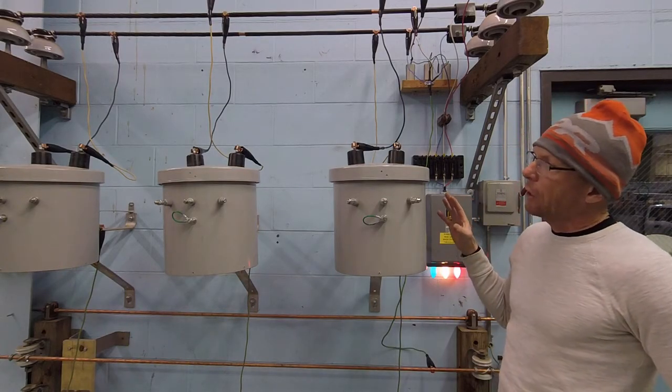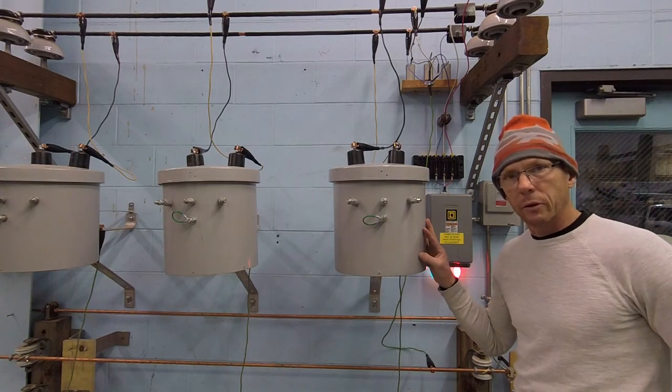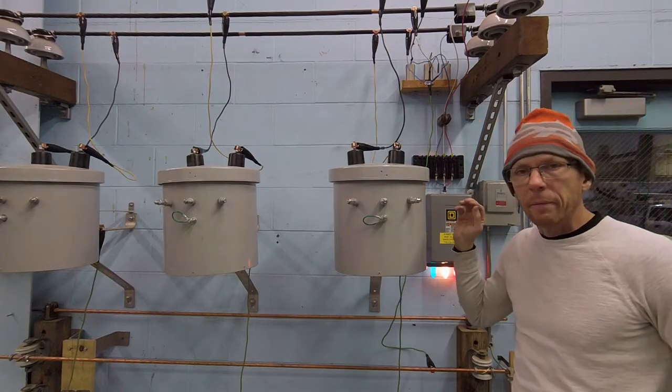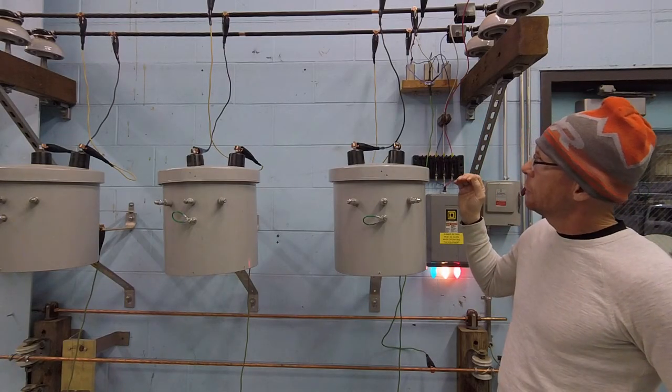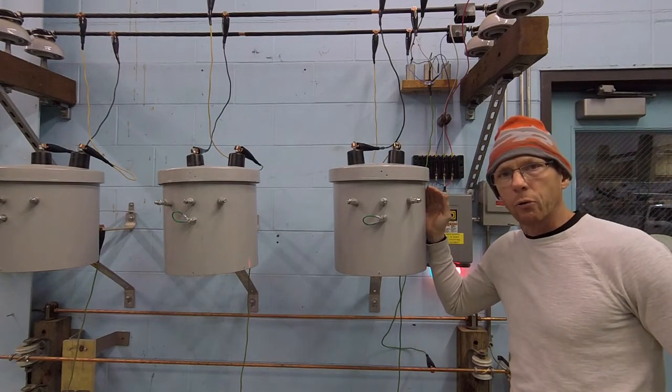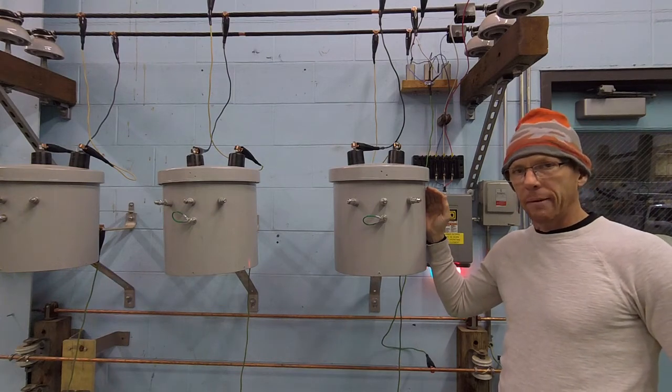When I create a circuit that causes one or more of these transformers to go into resonance with the capacitance of the source that's feeding it, the voltage from a resonating transformer to ground or neutral can double, triple, or quadruple in magnitude.